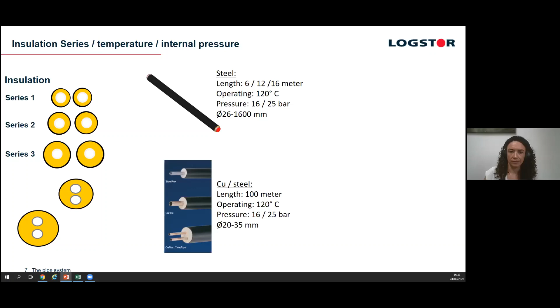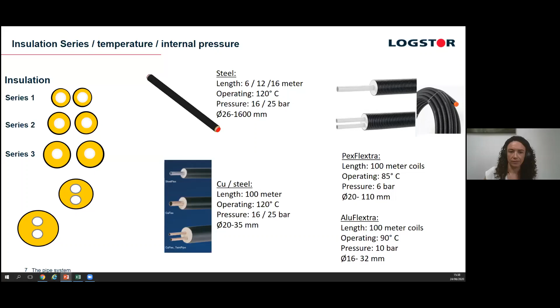Do you want it in copper or steel? What are the lengths? And then you've got different operating and temperature considerations. So for example, if you wanted to have an 85-degree system, fairly lowish temperature, then you could use the Aluflex or the PEX, but you must then bear in mind what's your operating pressure. So for example, the PEX would go up to 6 bar, Aluflex up to 10 bar. If you're outside of those, you've got to go with steel basically. You haven't got any other option.